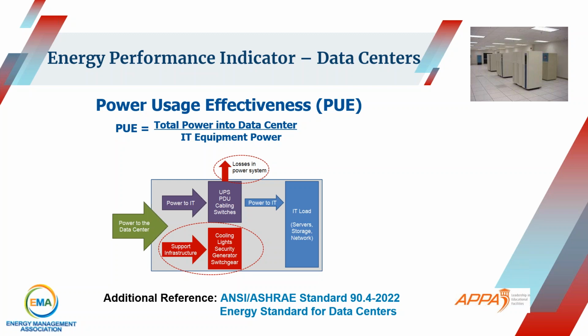To give you an idea, probably about 15 years ago a data center might have had a PUE of 1.6 or 1.5. Today there have been great strides made, and a perfect PUE would be 1.0, meaning all the power input to the data center would be used strictly for IT equipment. Google's average PUE is actually 1.1 right now. At the bottom I've shared an additional reference from ASHRAE, standard 90.4-2022, which is a standard for data centers, basically a companion standard to 90.1.